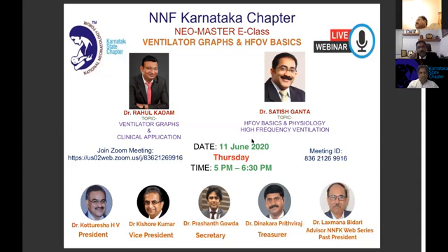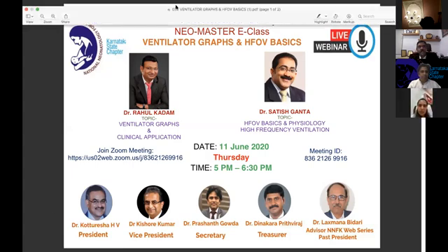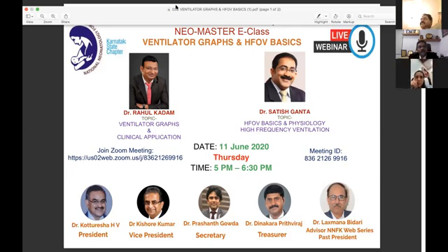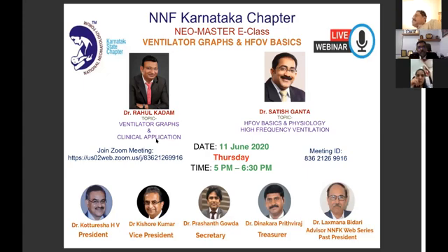The second thing is, the trigger sensitivity is the most important. Whenever a negative pressure is created in the circuit, that is how these ventilators sense that the baby wants to breathe, and that is when it will give the breath. So usually it is the inspiration which will be synchronized. But the pressure support ventilation mode has come mainly because of this reason. Suppose you are giving a breath to the baby, and at that point the baby wants to exhale. The baby will not be able to exhale. Whereas if it is on pressure support ventilation, it will immediately sense that the baby wants to exhale, and it will cause flow termination, and this is how synchronized expiration also happens in pressure support ventilation. I hope I'm clear with this.